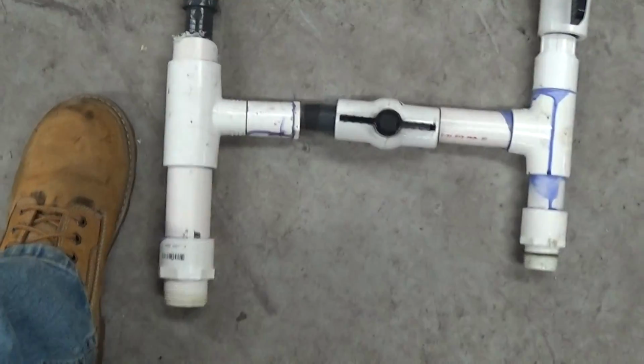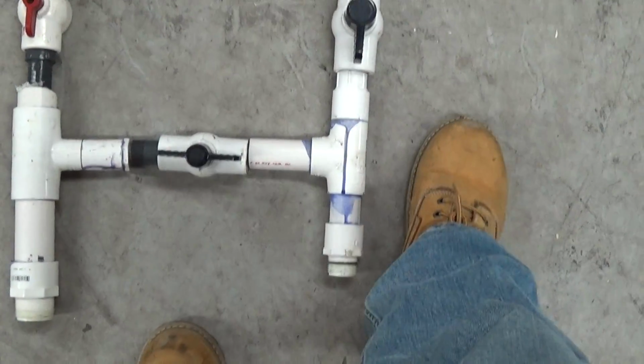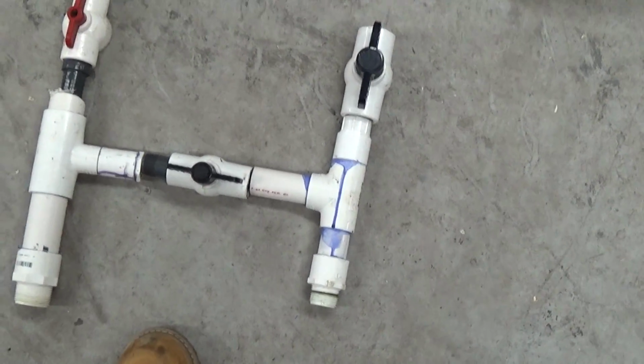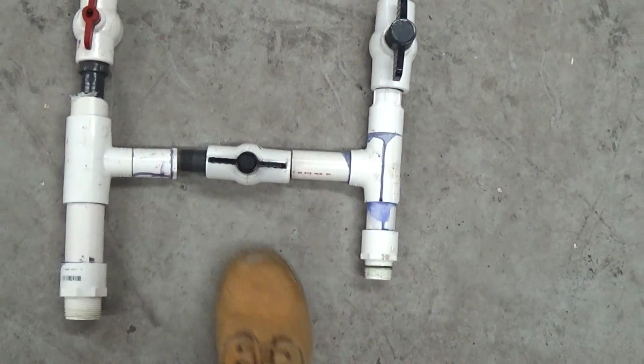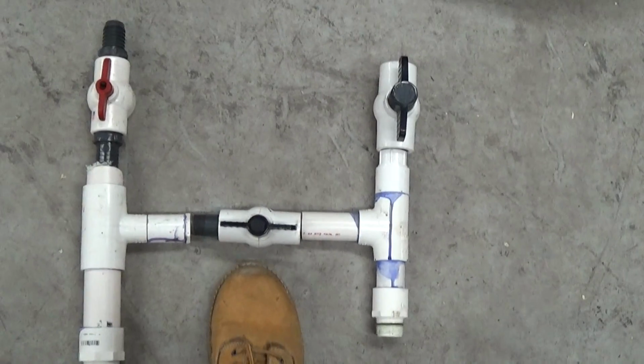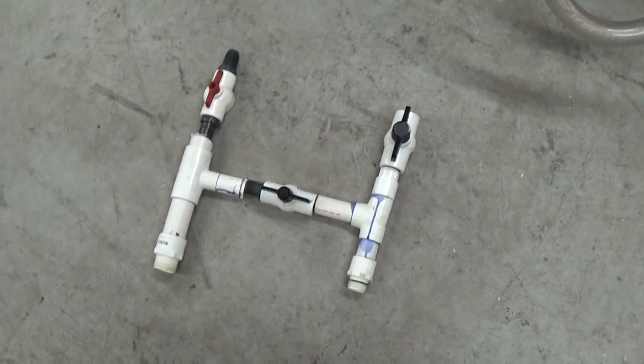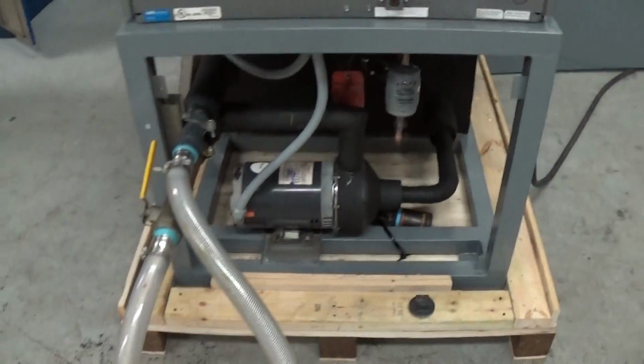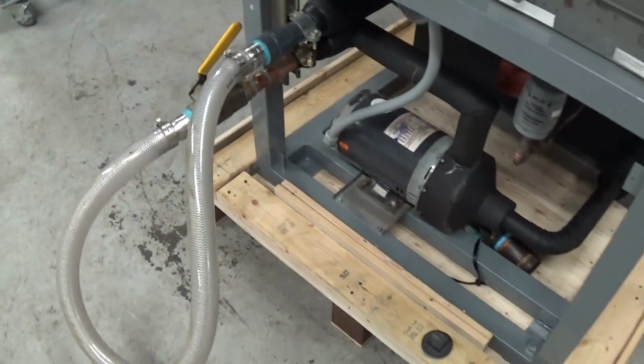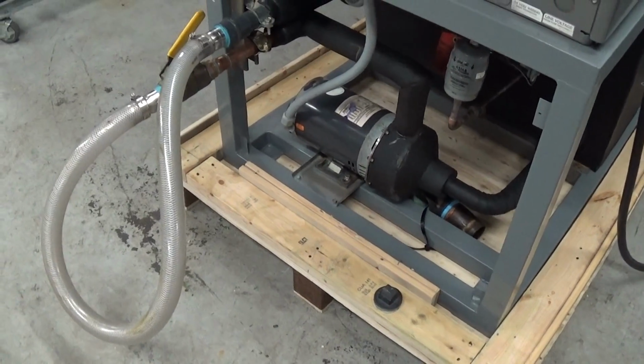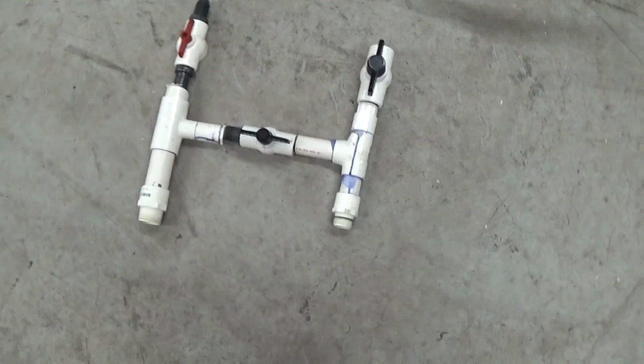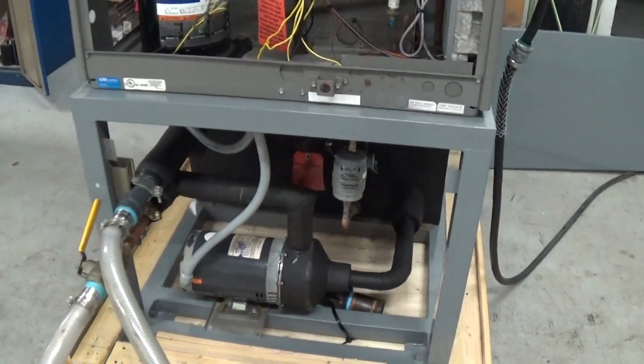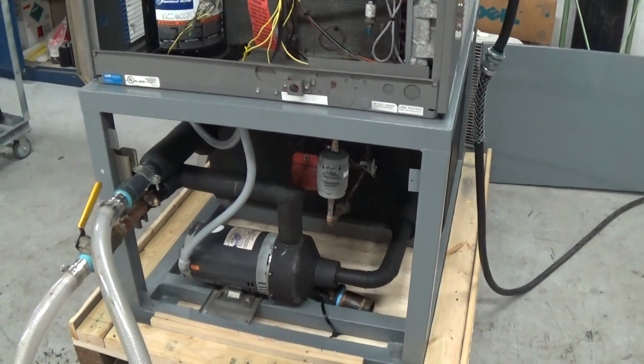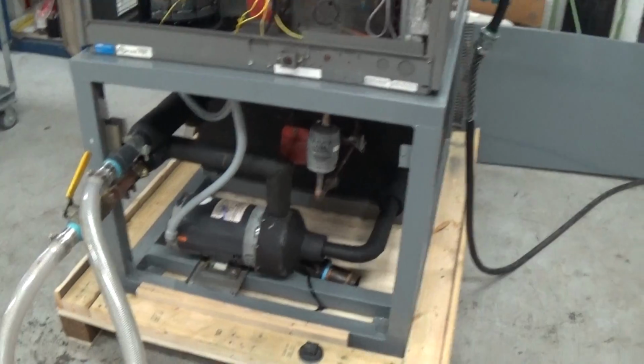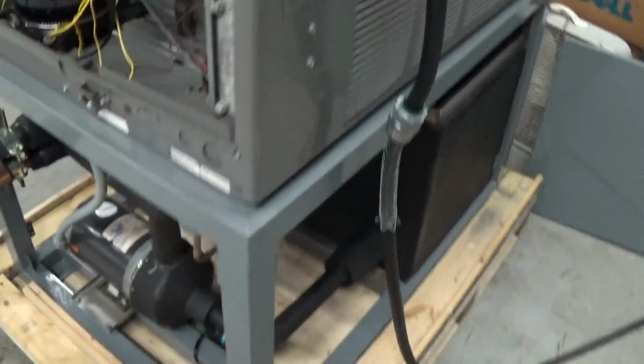Then put some T-fittings, okay? And this can be brass or Schedule 80. And hose, and then connecting those two T-fittings, you want to make a line and put another shut-off there. That's a flow bypass. So if you're pumping out to your process and your process is either too restrictive, or if your process even closes up completely sometimes, that's when you would tweak open this bypass to make sure your chiller has enough flow returning back to the heat exchanger, because what you don't want to do is stop or minimize the flow and pressure back to the chiller.